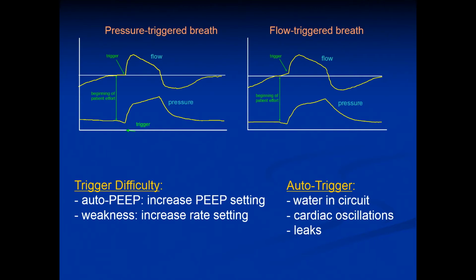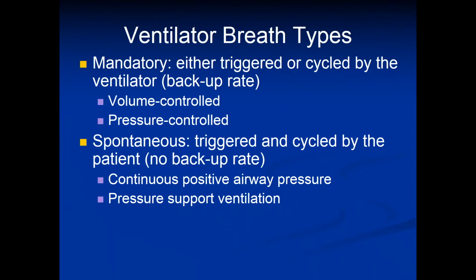We can also see auto-triggering take place due to water in the circuit or circuit leaks, and occasionally cardiac oscillations may cause the ventilator to trigger due to the pressure oscillations within the system. So what are the different breath types available on a ventilator? Well, the breaths can be either mandatory or spontaneous, and with the mandatory breaths, they can be triggered or cycled by the ventilator with a backup rate. These breaths can be either volume controlled or pressure controlled.